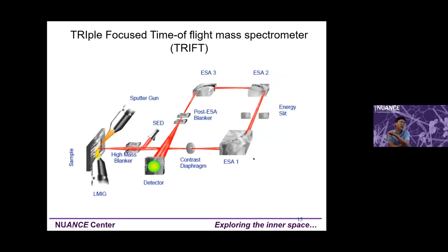Now let's look at the ToF-SIMS instrument schematic. We have the sample, a liquid metal ion gun for analysis, and a sputter gun — we can use gas guns such as cesium, oxygen, or argon — to sputter the surface for depth profiling. After sputtering, the analysis gun collects the secondary ions, which then go through an electrostatic analyzer (ESA) to refocus over a certain flight distance to the detector.